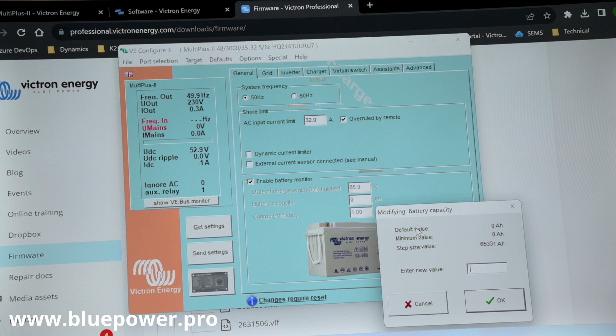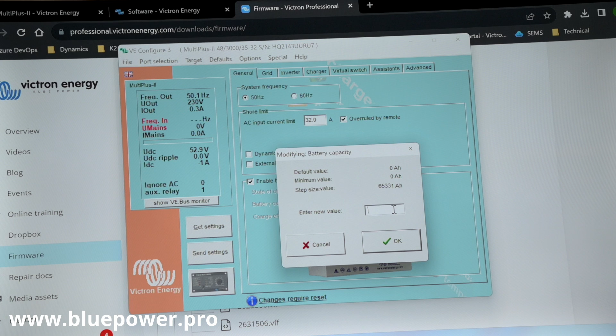First thing it's going to ask us is to modify our battery capacity. That's the size of our battery. Over here we've got a 100 amp hour battery, so that's the amp hour rating we have to input. Next we've got state of charge when bulk finished. This is the state of charge at which the inverter is going to switch over to absorption state. Lithium batteries require to be charged at constant voltage, constant current up until 95%. So for any lithium battery, that value is 95%.